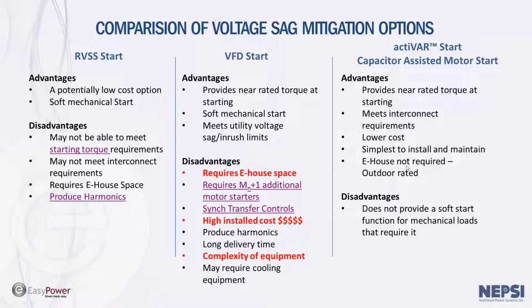It is by far the lowest cost option when considering the actiVAR; it's nothing more than a shunt power capacitor bank. So in terms of maintenance, it's much simpler to maintain when compared to a VFD starter. It's a shunt connected device and therefore does not require any bypass breakers or bypass switches. It does not require an E-house because it's outdoor rated. The key disadvantage to the actiVAR is it does not have a soft start function. We are basically supporting the bus voltage to 1 per unit, and you're applying the motor as an across the line start, and therefore the motor gets full torque.